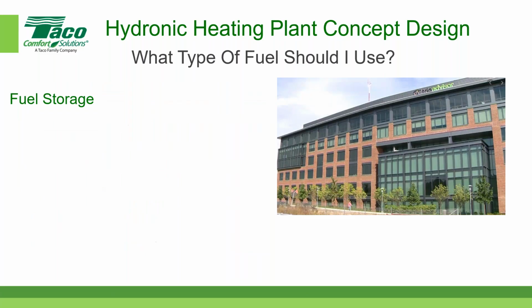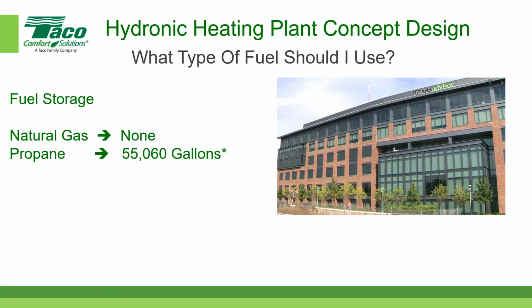Okay, so when it comes to different types of fuel, we have to think about fuel storage. Natural gas does not typically have any on-site fuel storage. Whatever is in the pipe is what's available for your heating system in your building. For propane, we might consider storing 55,000 gallons. You'll see where I got this number in a minute. And for number 2 fuel oil, we would want to store about 41,000 gallons. What we're saying basically is 41,000 gallons of fuel oil would have the same heating capacity as 55,000 gallons of propane. So that's what those numbers are telling us.